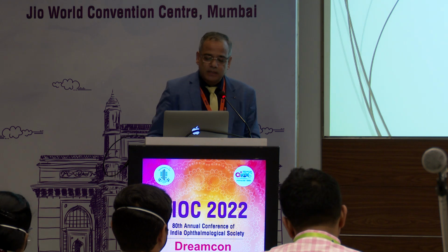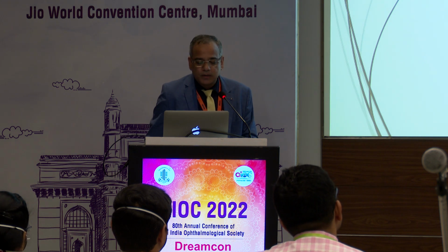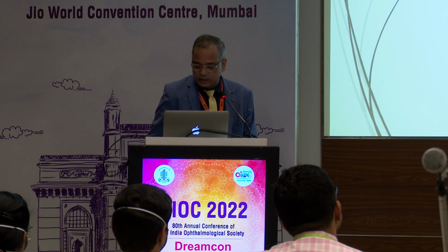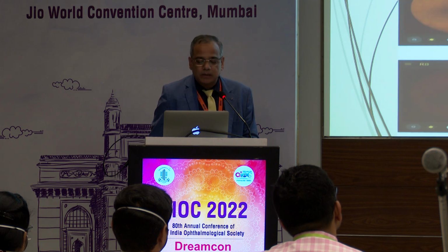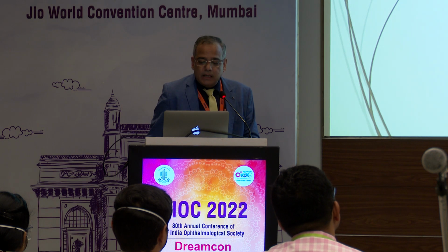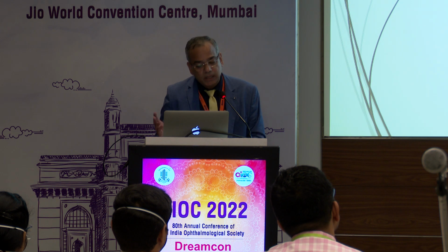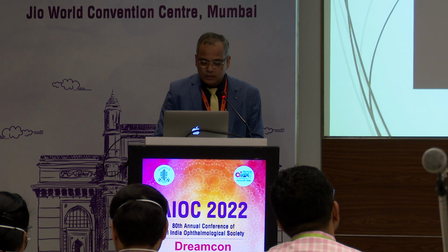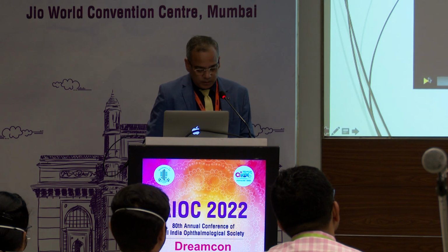It has many special features like the zoom capacity of 3 options, green channel for red-free image, and brightness and contrast slider to make the ungradable images gradable, and a smarter image compression format that is WebP, so it maintains resolution of images but keeps a low memory footprint. So it's a small video.